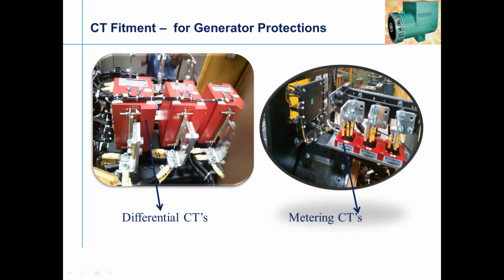Thanks to the latest technology of the designers, they give the differential CT inbuilt in the generator terminal box. Historically, this was not there in the 90s. It was being put in the panels. Today, everybody talks about compact design and other things. So re-engineering, or value engineering, happened to accommodate everything in the generator. This is one of the innovative ideas where, on customer demand, these protection CTs, as well as the metering CTs and the differential CTs, are put in the generator. So it is very, very important to the system requirement.